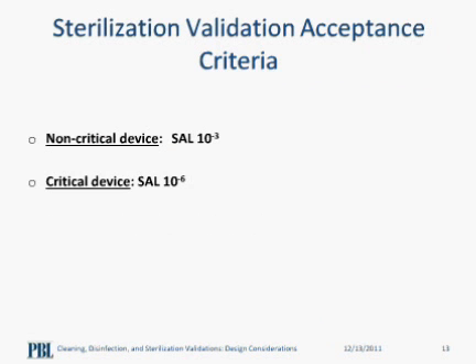The acceptance criteria for a sterilization validation is pretty straightforward. For a non-critical device, an SAL of 10 to the minus 3 is acceptable. For a critical device, a SAL of 10 to the minus 6 is required.